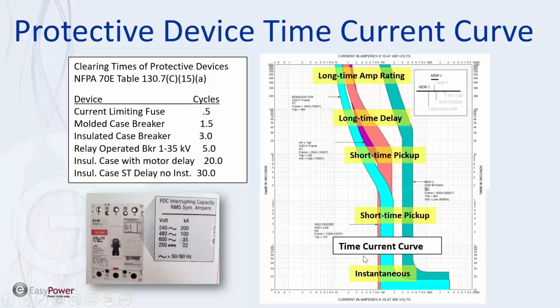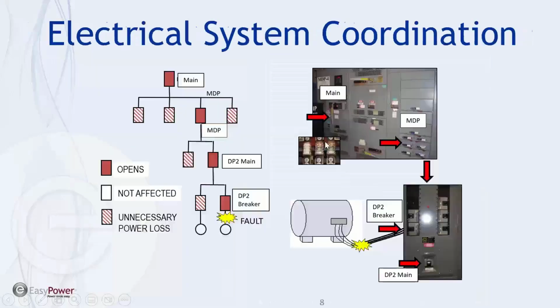If you look down at the bottom, you'll notice the first one tripping is going to be the orange one. The orange one is the main distribution panel. If the main distribution panel goes, there's a lot of load downstream, and I'm going to show you what that looks like. So these are the different panels. These are the time current curves that we just looked at.